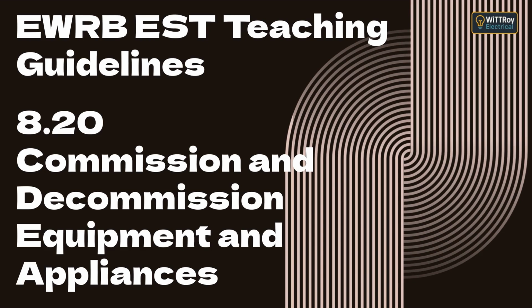Topic B. Precautions when disconnecting or reconnecting different cable types. Now let's move to Topic B. Precautions for various cable types. Different cables require different handling to prevent damage or unsafe connections. Let's speak through the common ones listed in your guideline. 1. TPS, tough plastic sheathed cables, very common in fixed wiring. Avoid nicking the insulation when stripping. Keep the outer sheath under the cord grip inside the enclosure.